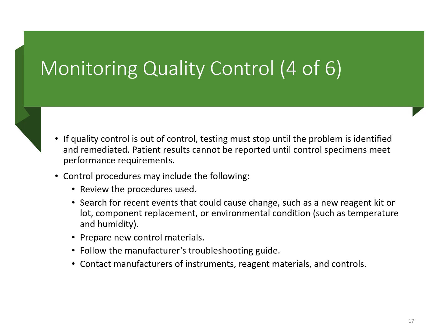Did you just make up new control materials? Maybe you pipetted too much deionized water into your control material. Maybe there's something on the machine that's messing up. Maybe, like I mentioned earlier, something in the temperature of the room or humidity is changing at a certain point in the day, so you need to look at environmental factors. So you would go through a process of trying to evaluate and troubleshoot.